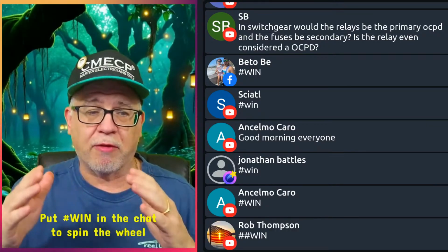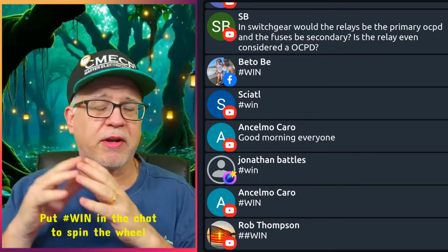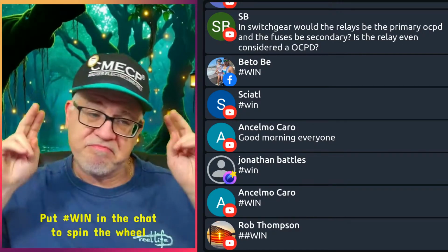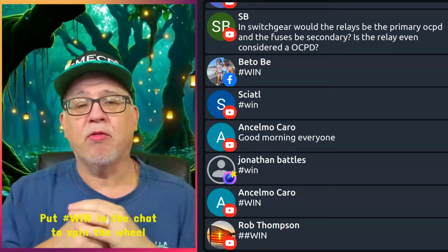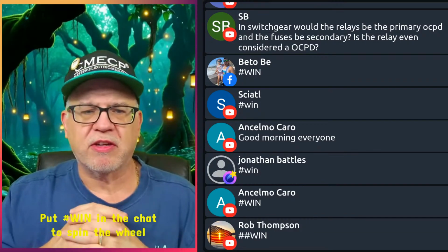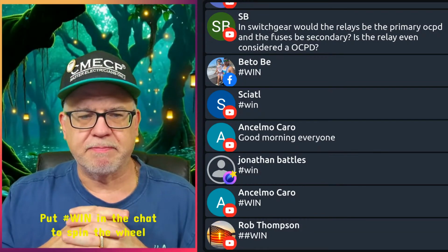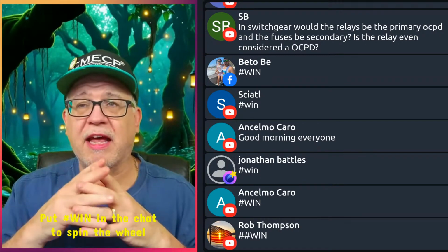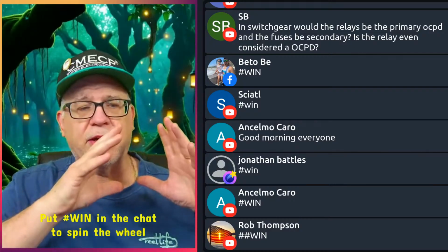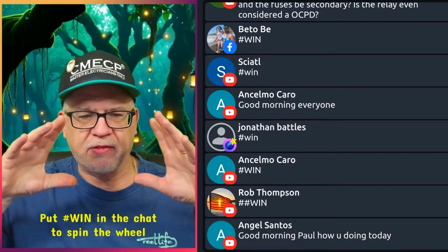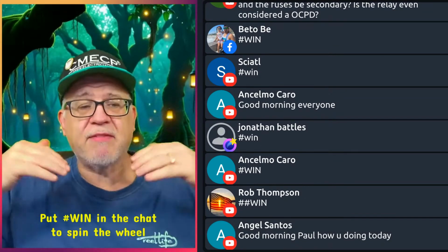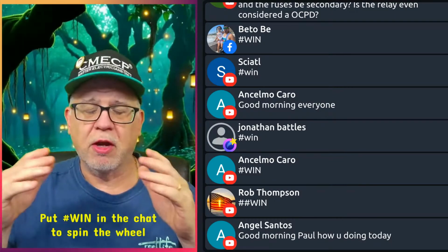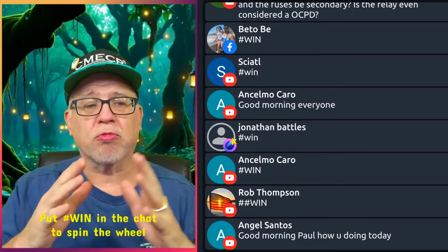And that can branch off into the different legs where they can have their own separate overcurrent protection. But if you have something ahead of all that, then that is your primary overcurrent protection. And of course, nothing says that you can't have secondary protection downstream. Usually that secondary protection is very specific to the circuit it's serving. So with a lot of this gear, you may have a main breaker that protects it and feeds a bus. And then underneath it, you may have internal branches or taps within the equipment or switchgear, which may drop it down to a lower rating.